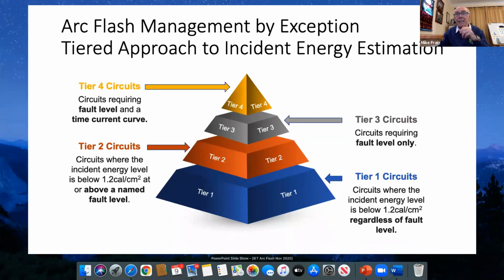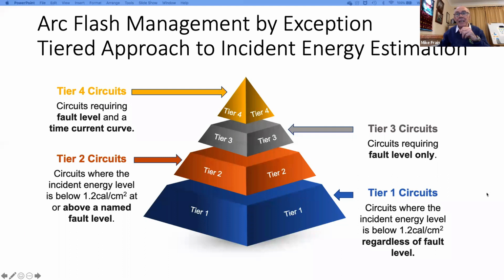And in this particular case, they would be called tier 1 circuits. So it's where the incident energy level is below 1.2 calories. And within the guide, we can tell you what circuits they are. And you don't need fault level either to work those circuits out. There's a caveat or two to take into account, but that's all explained there. Tier 2 circuits are where incident energy level is below 1.2 calories at the equipment, above a named fault level. And I'll explain that. You might not know what that means until the next slide.